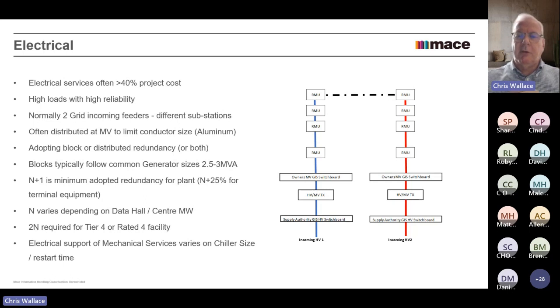A ring main unit, for anyone who doesn't know, is normally a medium voltage unit where you have an incoming supply and an outgoing supply, which allows you to form the ring. And then between the incoming and the outgoing supply, you have a tap off, which allows you to feed the load. I'll show you in the next slide what you have.